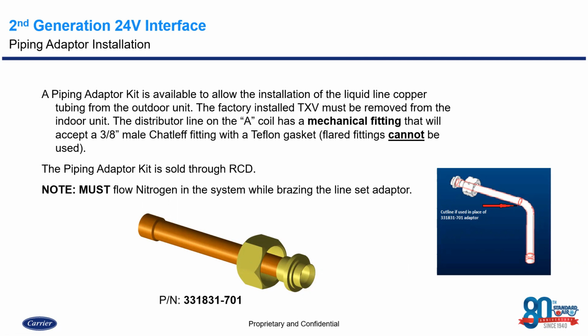Okay, so part number is below for that male Chatleff fitting on there, and you can see on the one end of here that this is swedged out, essentially telling you that you either have to braze and or press on the system.